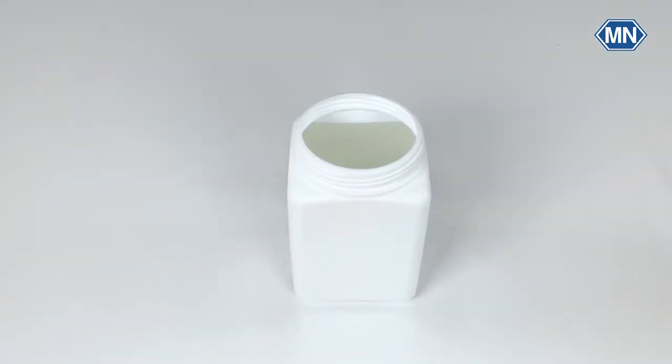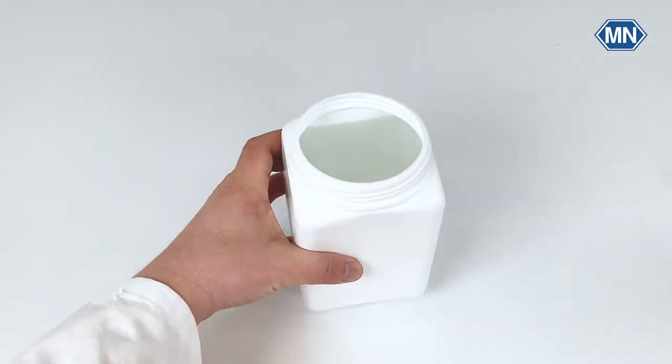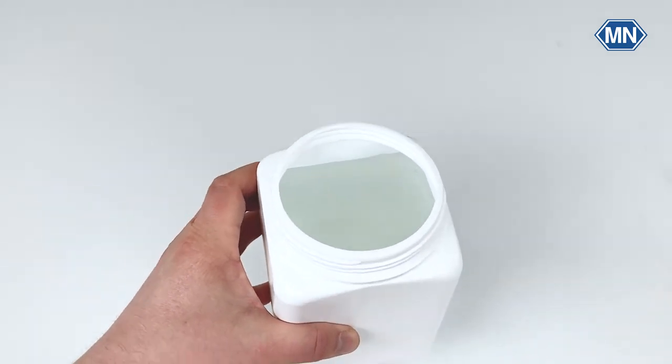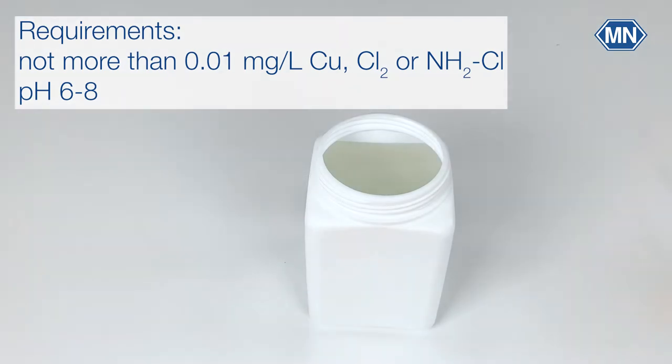Fill the storage vessel with water. For this you need unchlorinated tap water. The water must not contain more than 0.01 mg per liter copper, chlorine or chloramine. The pH value should be between 6 and 8. If necessary adjust the pH with sulfuric acid or sodium hydroxide solution.